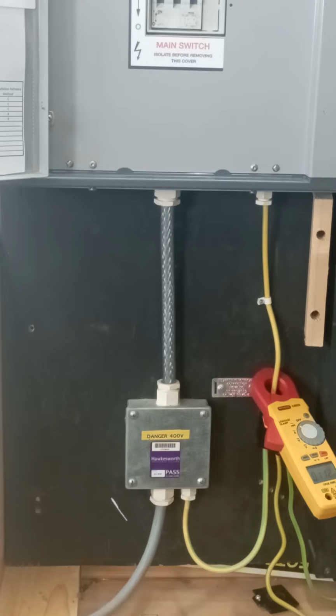For the installation, as I said, what's happening there is we're getting some protective conductor currents passing through those sensitive electronics that are further downstream. Within the installation, obviously after we've done that, we're going to be moving on to our live working, so we'll get the board prepared for live working.